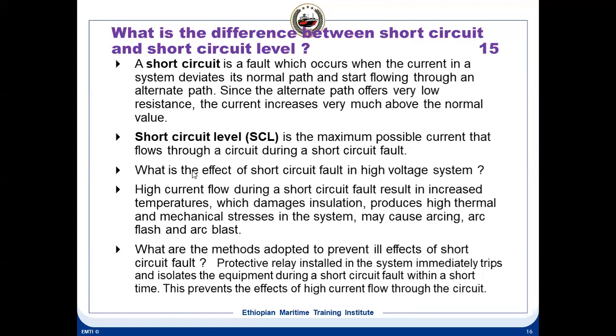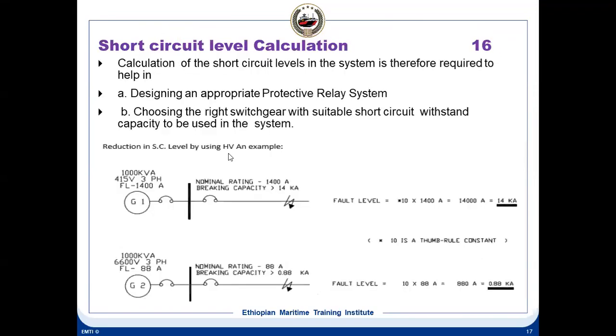So what are the methods adopted to prevent the ill effects of a short circuit fault? To protect against short circuit faults, protective relays are installed in the system. They immediately trip and isolate the equipment within a short time during a short circuit fault. This prevents the effects of high current flow through the circuit, like fuses or breakers. These are all protective devices there to prevent short circuits. So hope this is clear: what is short circuit, what is short circuit level. Now, another important factor in the case of high voltage: the calculation of short circuit levels in the system is required to help in designing an appropriate protective relay system.